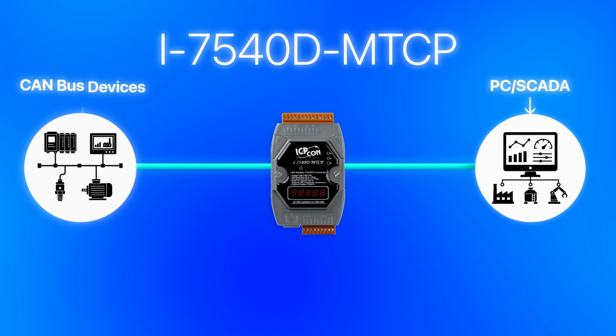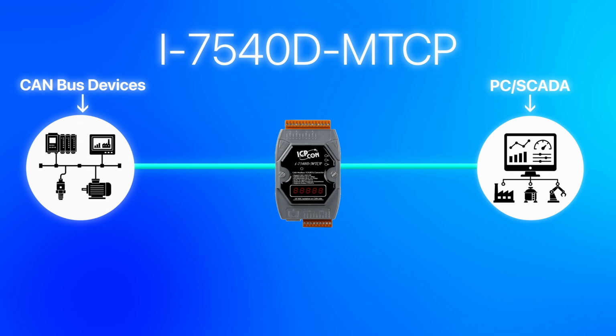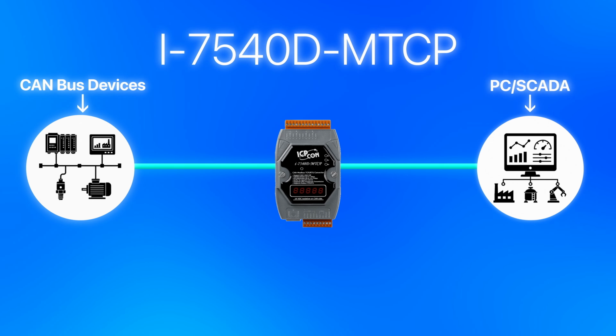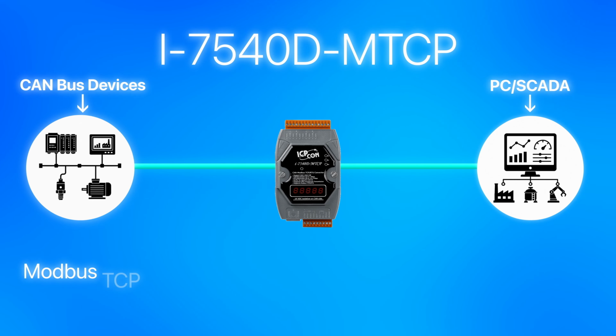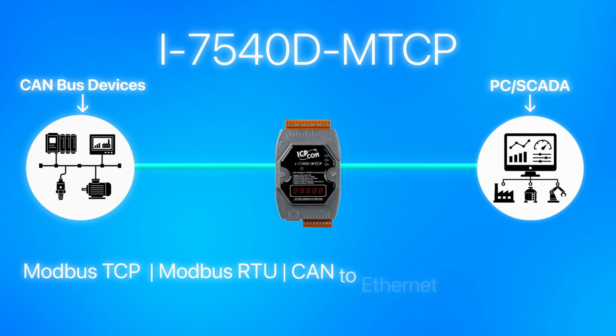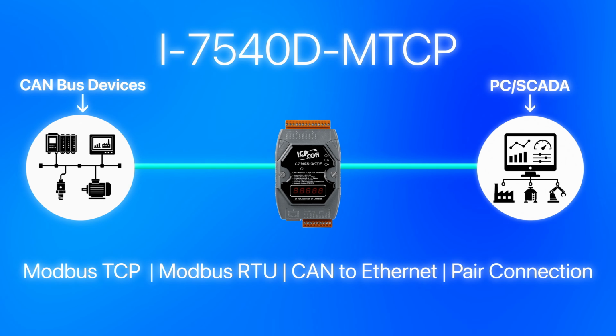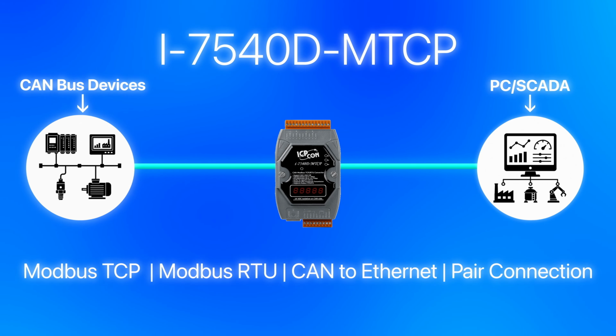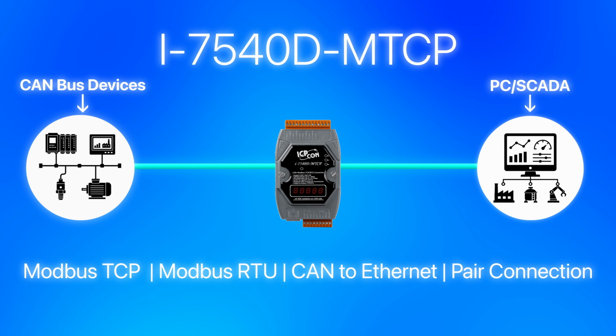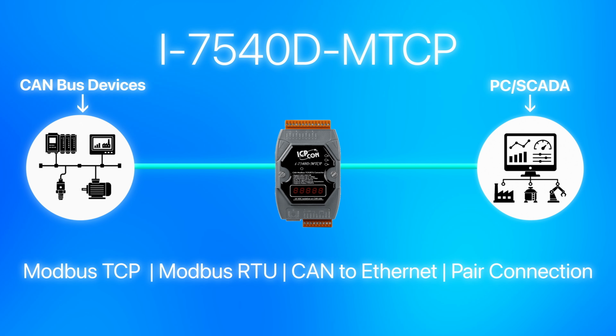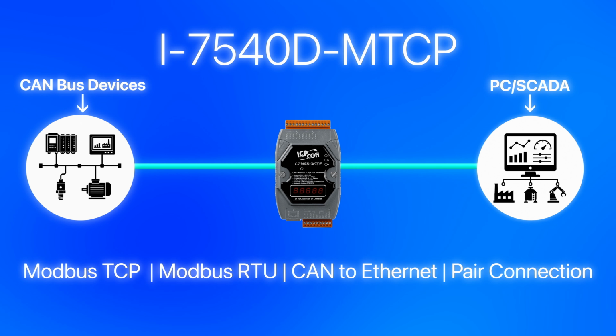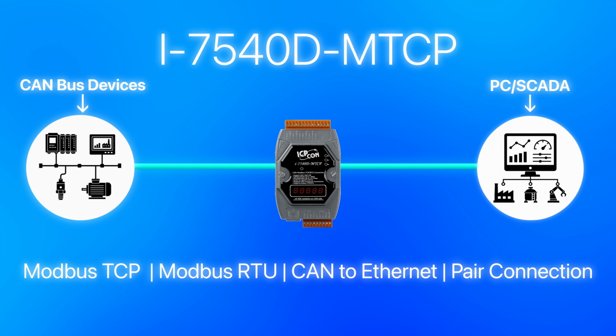It's a CAN to Ethernet and Modbus TCP and Modbus RTU converter that supports 4 communication modes, those being Modbus TCP, Modbus RTU, CAN to Ethernet conversion, and pair connection, which means any standard Modbus TCP client on your network can read and write CAN messages through it without any custom software. It supports higher layer CAN protocols like CANopen and DeviceNet on top of the CAN interface, so if your application is running a CANopen device and you need to get its data into a Modbus TCP system, this is the clean hardware path to do that.